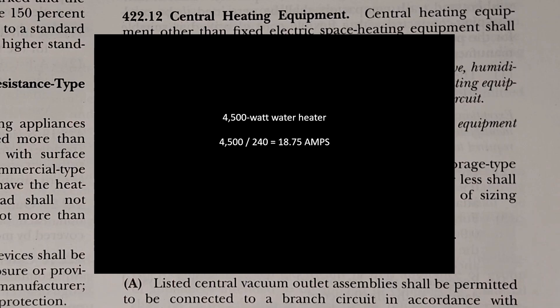A lot of people might think they can just go size their wire and breaker off this value, but that's not true. According to this code, we must take that value and multiply it by 1.25. That is increasing the value by 25%. Then we're going to size our wire and our overcurrent protection.